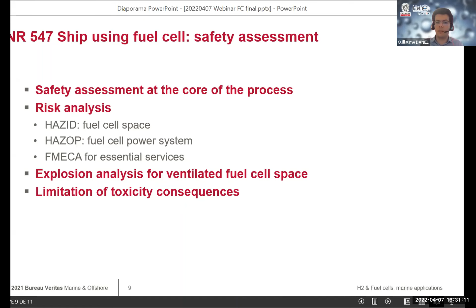There are different possibilities of risk analysis depending on those configurations, for example if it's used for essential services or not. You have to take into account if there is a need for explosion analysis, for example for ventilated fuel cell space. And possible toxicity consequences - it can be optional, it depends if, for example, you are intending to use ammonia or methanol. So it depends on the fuel, or if you are using a technology of fuel cells that can produce carbon monoxide, which can be toxic at some level.